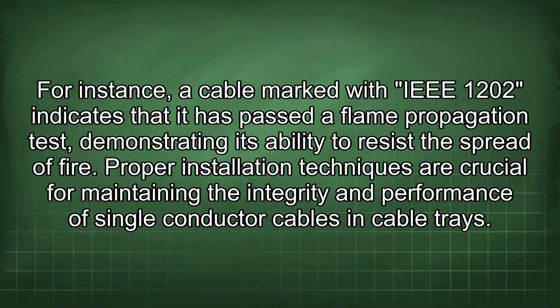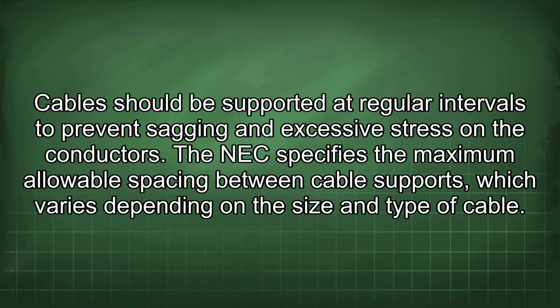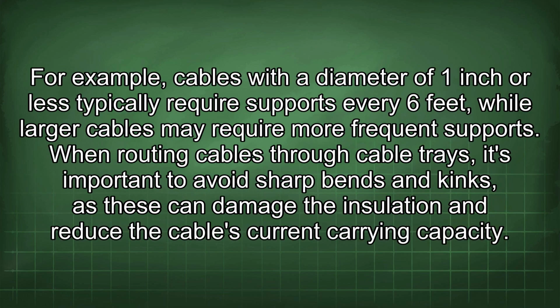Proper installation techniques are crucial for maintaining the integrity and performance of single conductor cables in cable trays. Cables should be supported at regular intervals to prevent sagging and excessive stress on the conductors. The NEC specifies the maximum allowable spacing between cable supports, which varies depending on the size and type of cable. For example, cables with a diameter of 1 inch or less typically require supports every 6 feet, while larger cables may require more frequent supports.